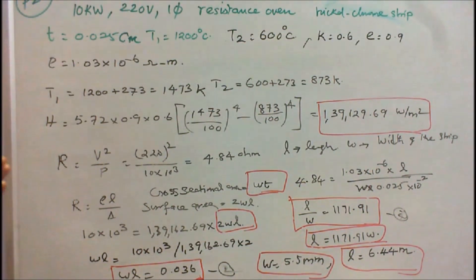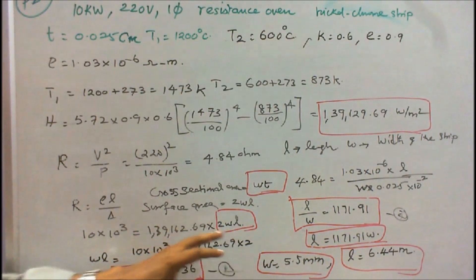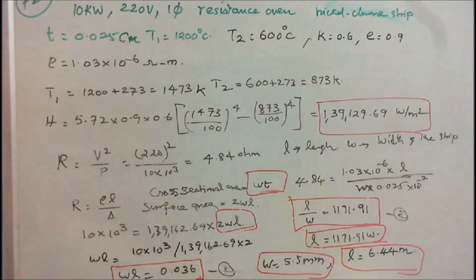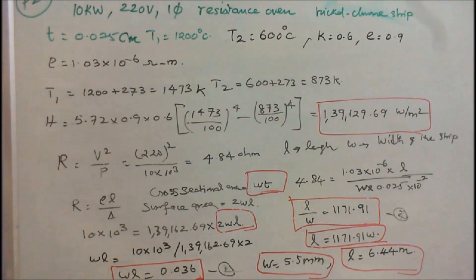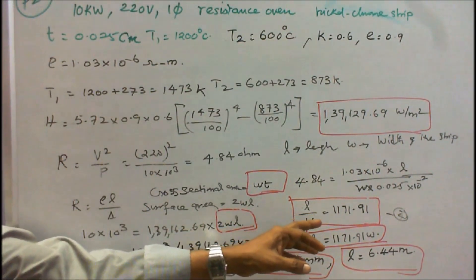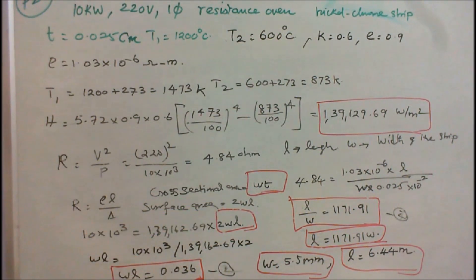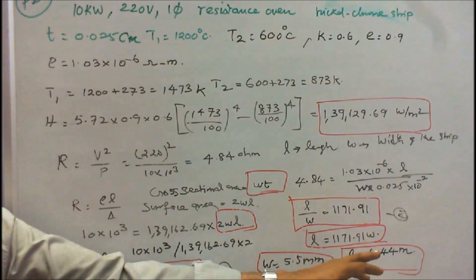Under thermal equilibrium condition, input power equals H times surface area. For a rectangular strip, surface area equals 2 × W × L. Substituting all values gives W × L equals 0.036. This is equation 2. Solving equations 1 and 2 simultaneously gives length L equals 6.44 meters and width of the strip equals 5.5 mm.